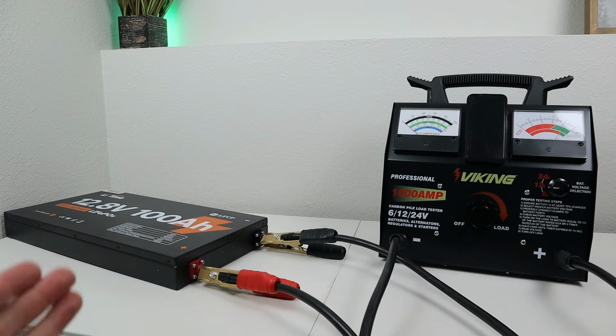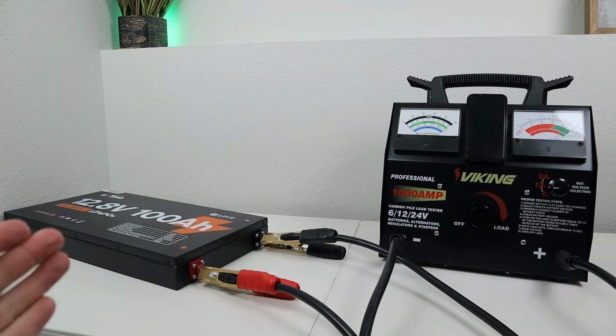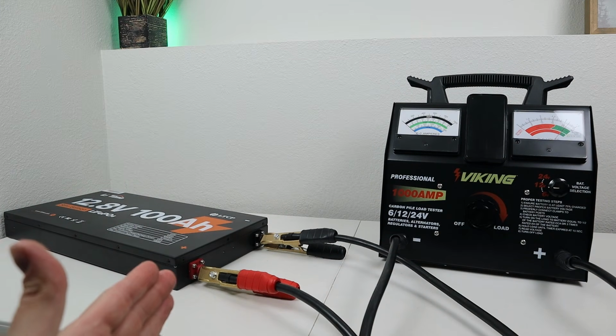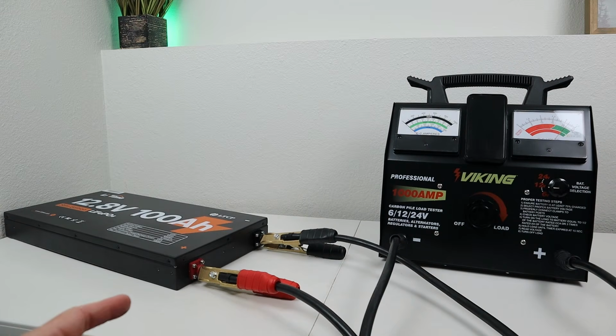So what did we learn? If you pull about 200 amps, it'll shut off after about 8 seconds. And if you ramp up the amperage gradually, it'll go all the way up to 600 amps before the BMS shuts off. So the BMS does have overcurrent protection.